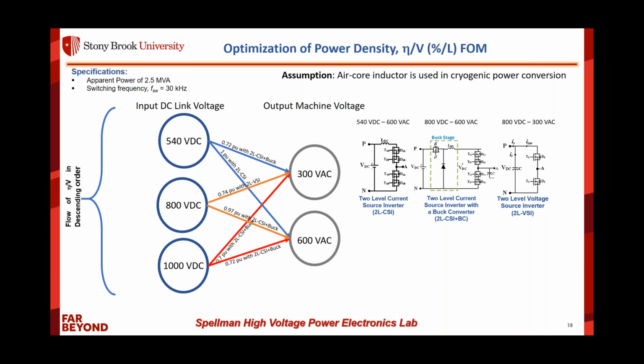We found that if I have access to cryogenic power conversion, the best figure of merit from the power converter combination comes from 540 volt DC to 600 volt AC power conversion. This lets me use a slightly higher voltage motor while still keeping the same low DC distribution voltage on the power system, using only a single stage, a two level CSI, to realize this power conversion. This gives the best figure of merit, close to one.